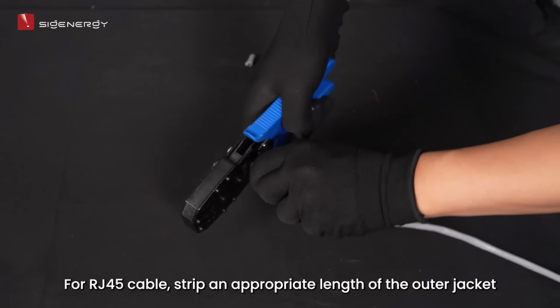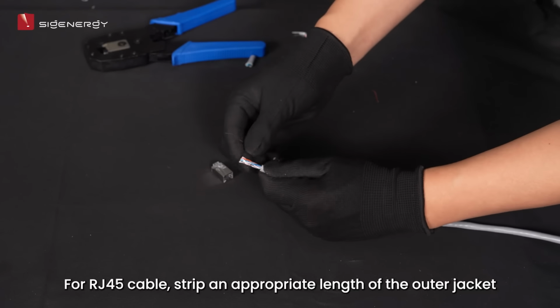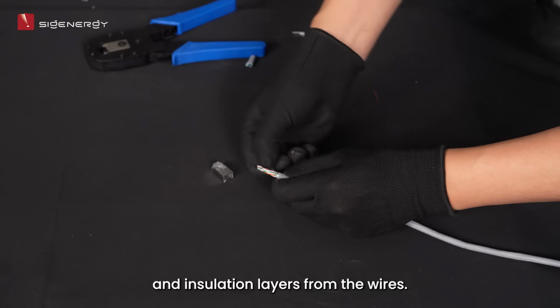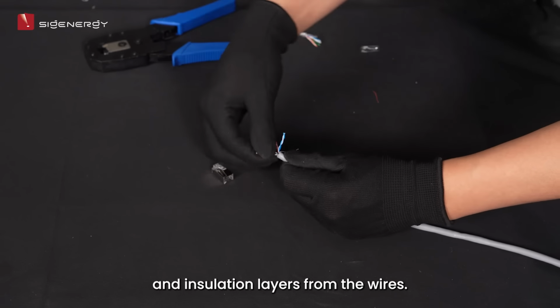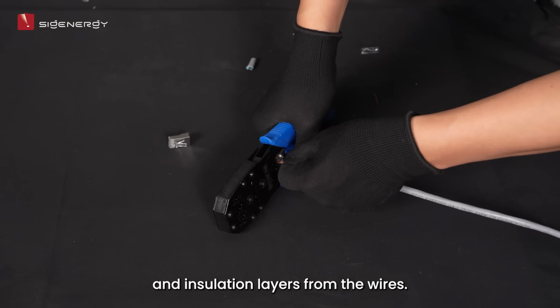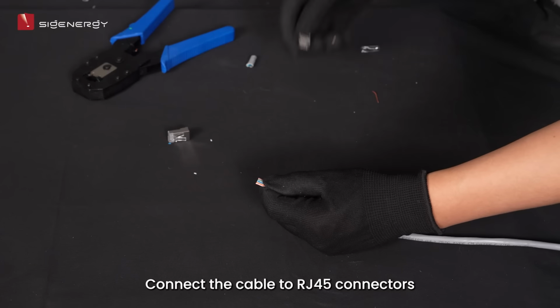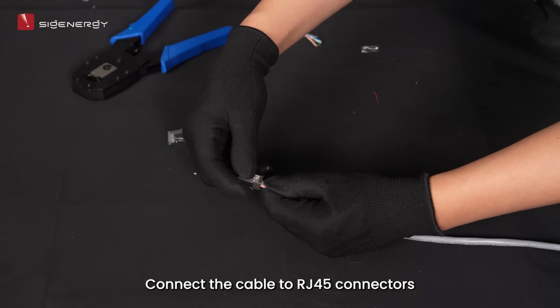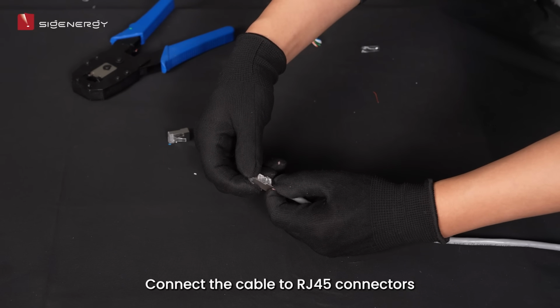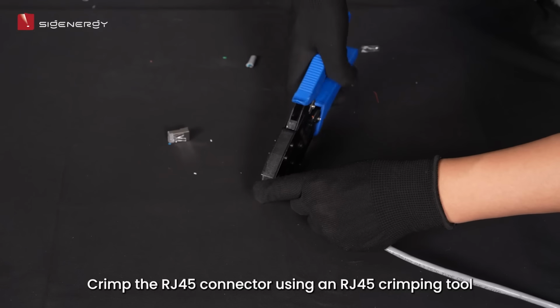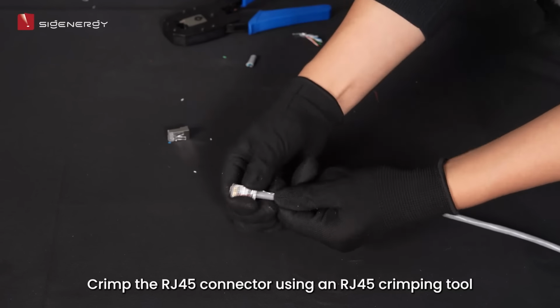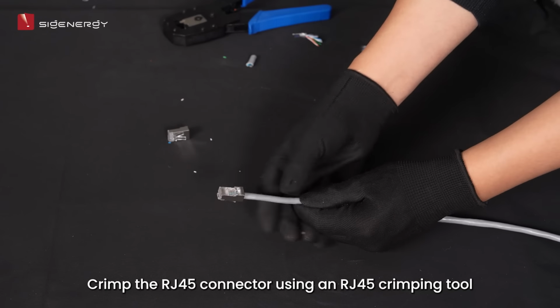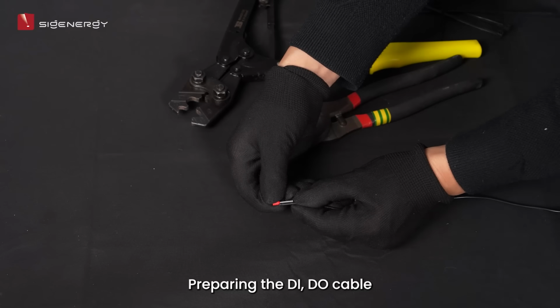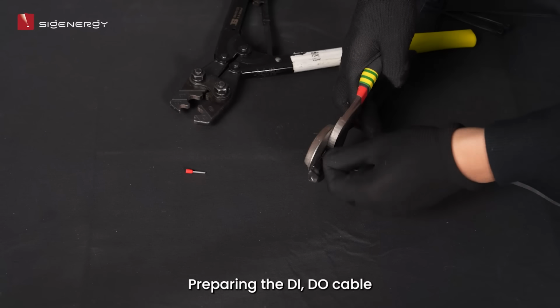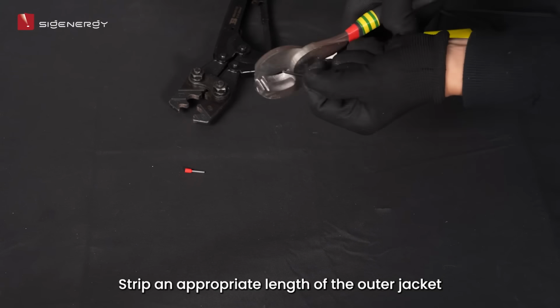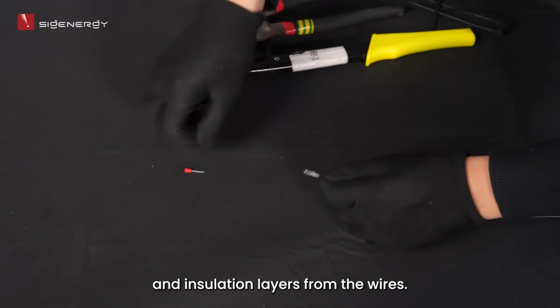For RJ45 cable, strip an appropriate length of the outer jacket and insulation layers from the wires. Connect the cable to RJ45 connectors. Crimp the RJ45 connector using an RJ45 crimping tool. Preparing the DI/DO cable. Strip an appropriate length of the outer jacket and insulation layers from the wires.